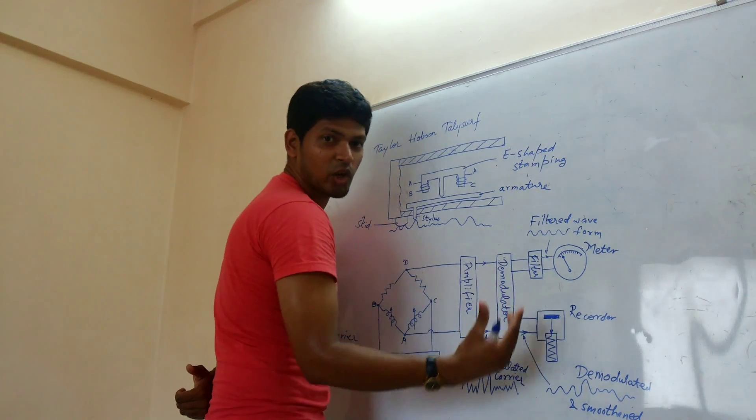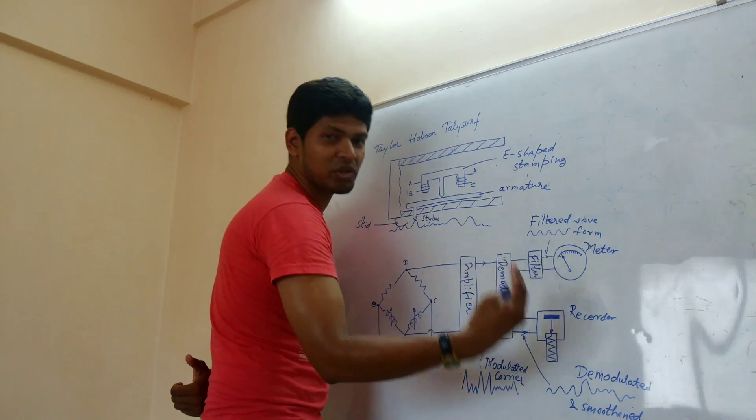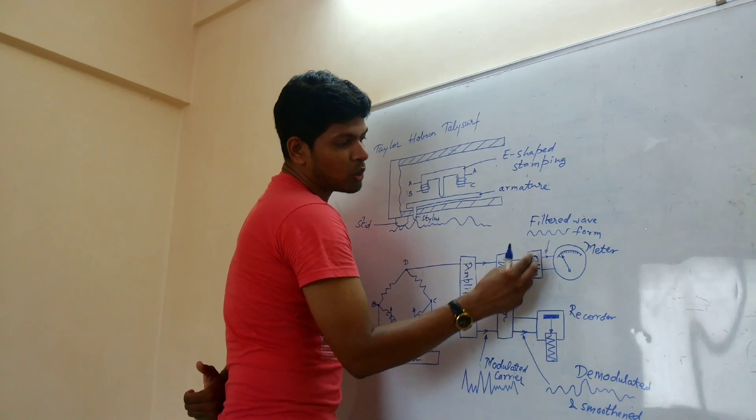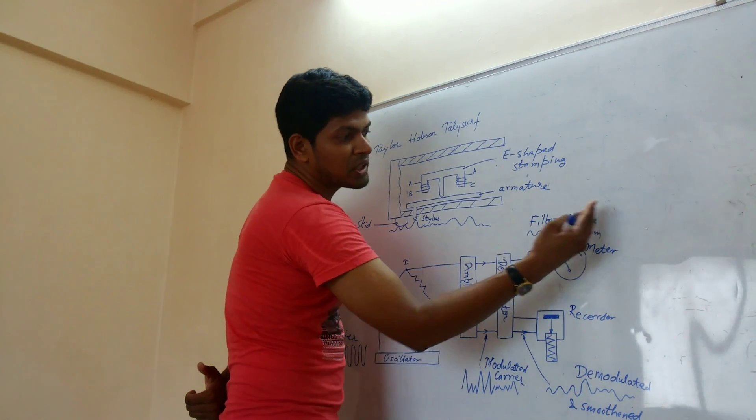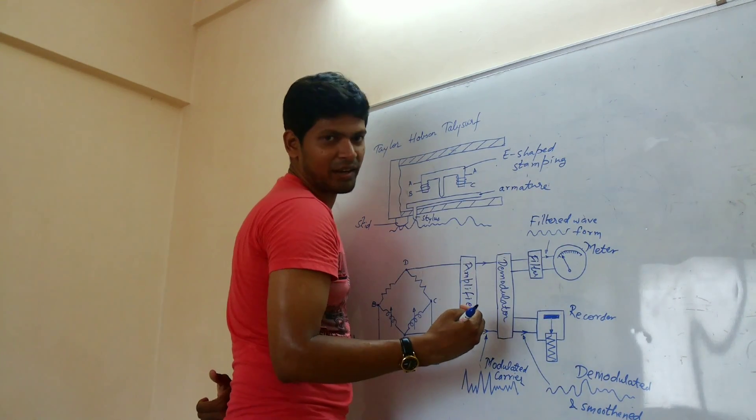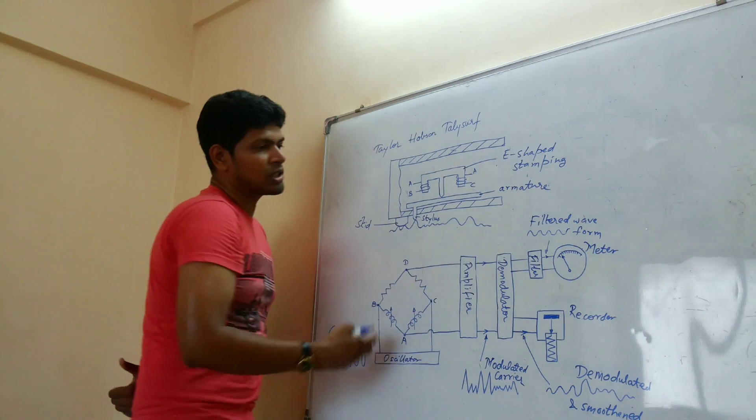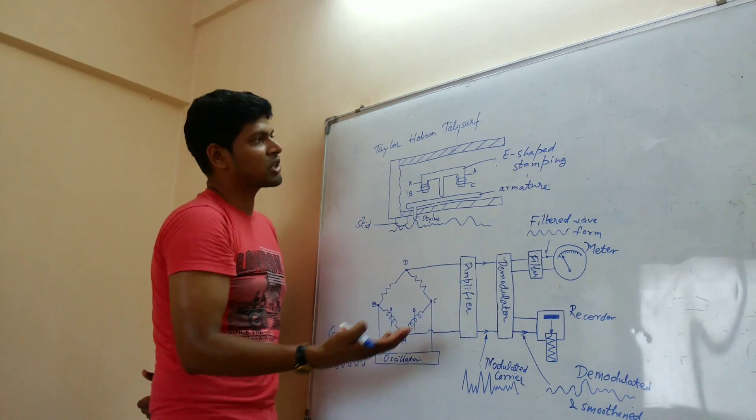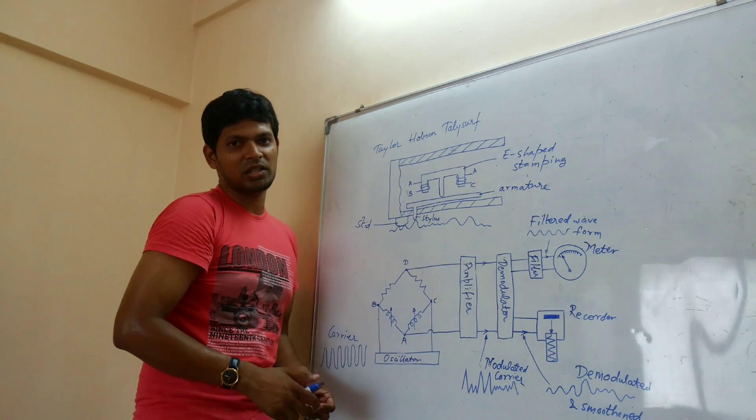And in the recorder you can record with the pen recorder for future reference. And also it gets filtered and you have filtered waveform so that you can have reading directly which you can view directly. This is the working and construction of Taylor Hobson Talysurf.